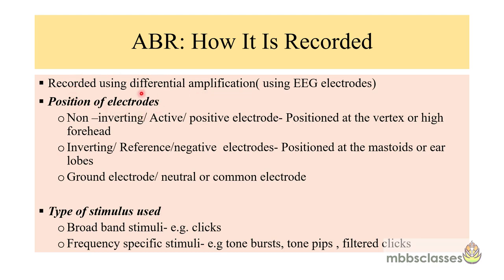ABR is a far-field recording, meaning it is recorded far away from the site of origin. There are three types of electrodes used. The first is the non-inverting or active or positive electrode, positioned at the vertex or high forehead. The second is the inverting or reference or negative electrode, positioned at the mastoid, ear lobes, or sometimes the nape of the neck. The third is the ground electrode, also called neutral or common electrode, placed most commonly on the cheek of the patient.